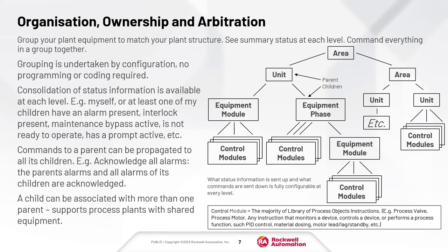So an area can contain another area, it can contain a unit, it can contain an equipment phase, for example. The diagram shows you what is a parent and what is a child in this structure. The control modules are the majority of the Library of Process Objects instructions - for example, the process valve, the process motor - any instruction that monitors or controls a device, or performs a process function such as PID control, material dosing, or motor lead-lag-standby control.